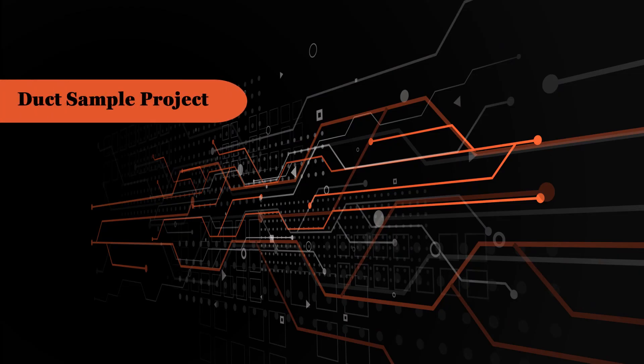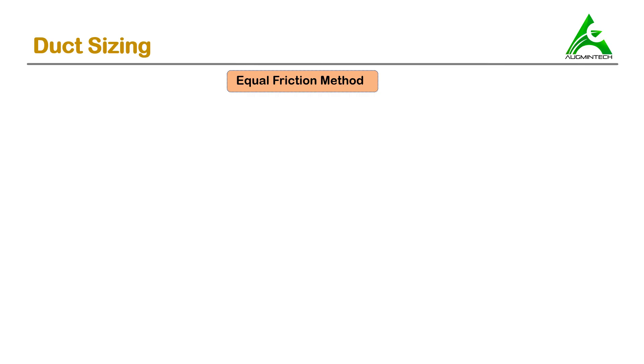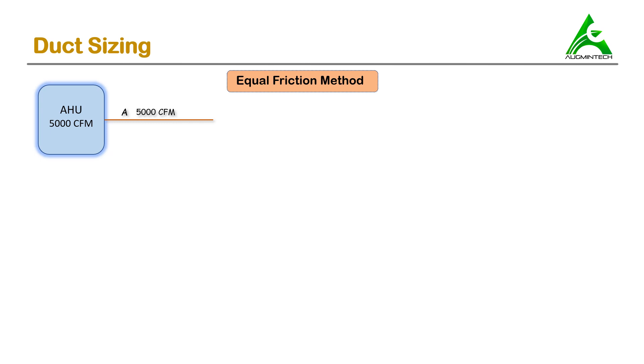Our topic for today is duct designing — a sample project of duct sizing using the equal friction method. There is an AHU of 5000 CFM capacity. This AHU provides 5000 CFM to the first section of the duct, which we'll call section A. From section A, 1000 CFM is taken by diffuser number one.